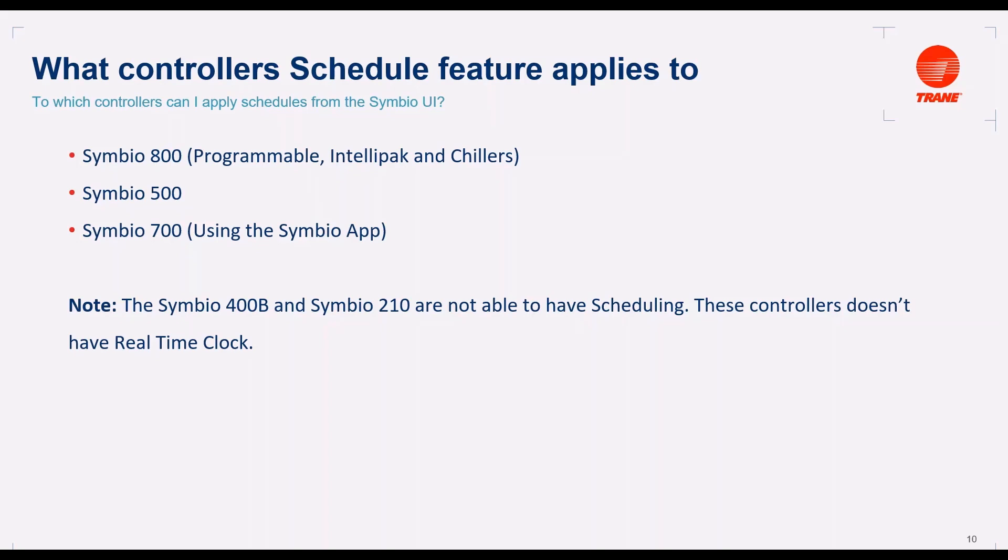An important note, the Symbio 400B and Symbio 210 are not able to have scheduling. These controllers don't have real-time clock, which is required for scheduling.